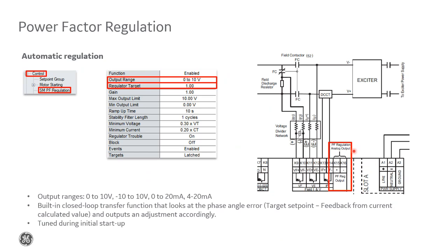And on the right here, we're showing the 869 relay's wiring diagram with the power factor regulator output on the right of the synchronous motor block option. So you can wire and set some of this as highlighted, but the exact tuning of this function is usually required to be done via testing during the initial startup period.